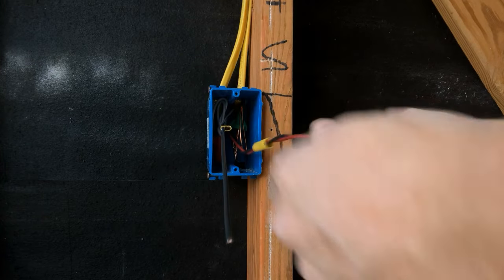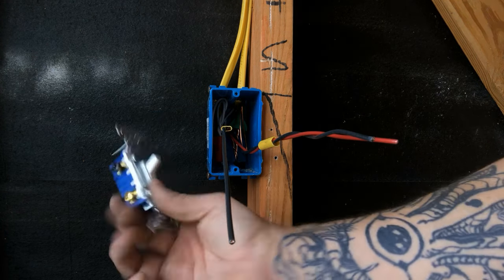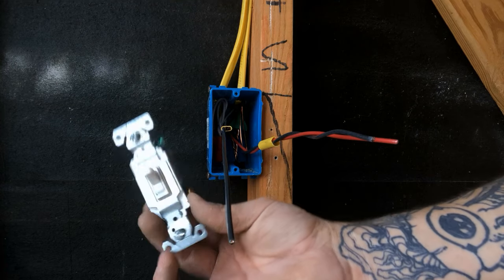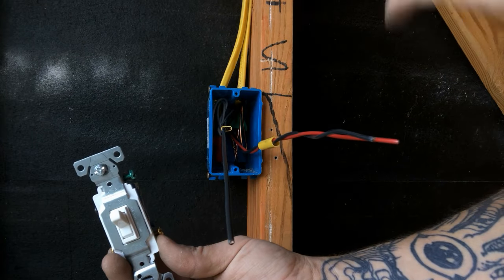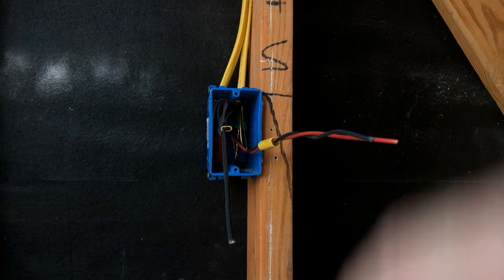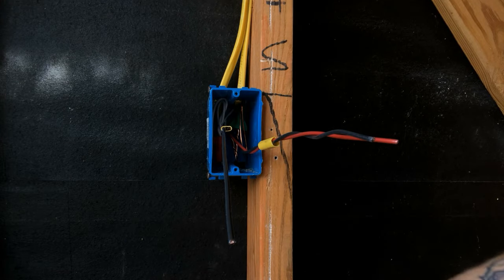The only thing we have left are the three wires that are ultimately going to go on our three-way switch. A four-way system uses two three-way switches and one four-way switch. You're going to have a three-way on the load side, a three-way all the way at the beginning on the hot side, and then you're going to have a four-way switch which goes in the middle.